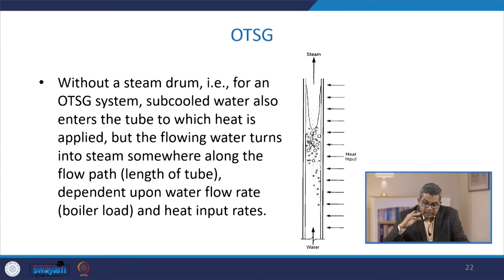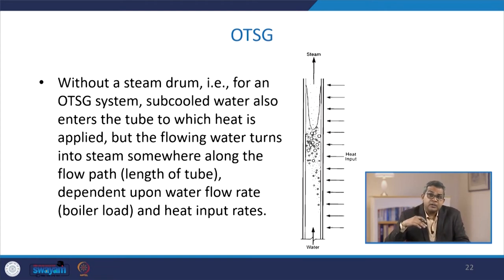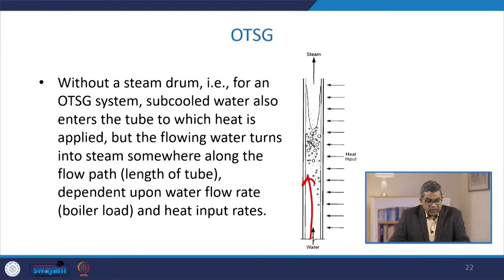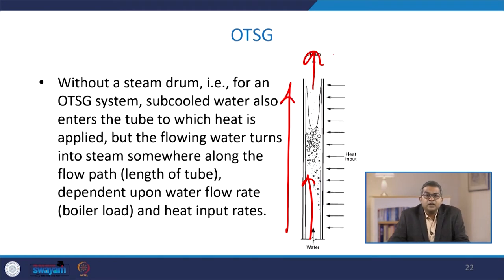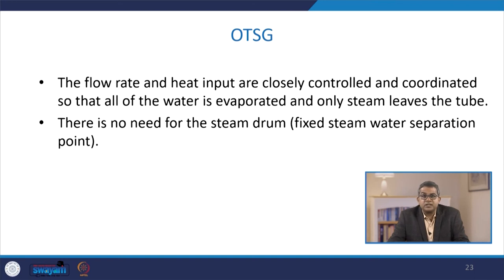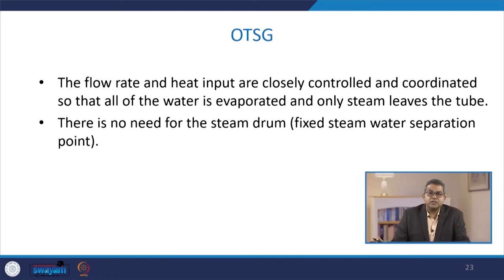Without a steam drum in an OTSG system, sub-cooled water enters the tube to which heat is applied, but the flowing water turns into steam somewhere along the flow path. This depends upon the water flow rate and heat input rate — these two are the variables for OTSG. The flow rate and heat input are closely controlled and coordinated so that all the water is evaporated and only steam leaves the tube, with no need for a steam drum or fixed steam-water separation point.